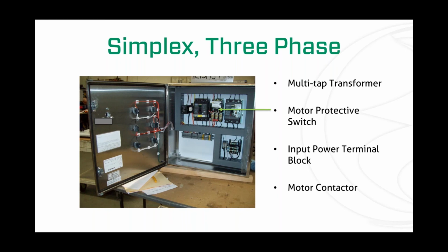The next thing we'll look at is the terminal block. This is where your incoming power goes, along with field wiring for your pump and float switches. You might have some auxiliary contacts in there too, like a pump run or high water alarm, and there could be a number of different relays. Your wiring schematic on the door will tell you that.